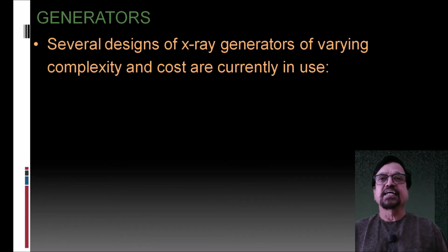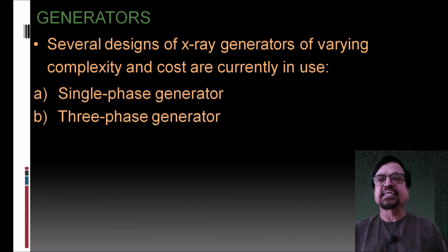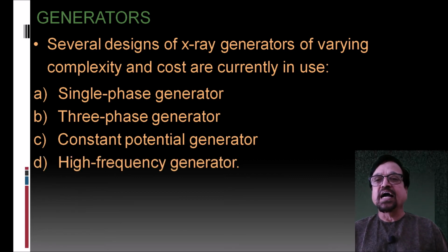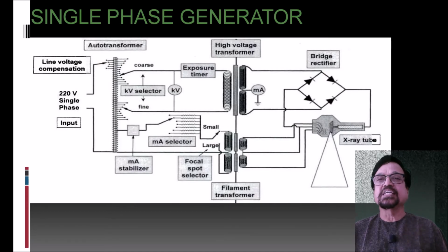Come to generators. Several designs of X-ray generators of varying complexity and cost are currently in use. There are single-phase generators, three-phase generators, and constant potential generators. Now, high-frequency generators are also available in recent X-ray machines. Now, these are the X-ray circuits by which these types of designs are achieved.